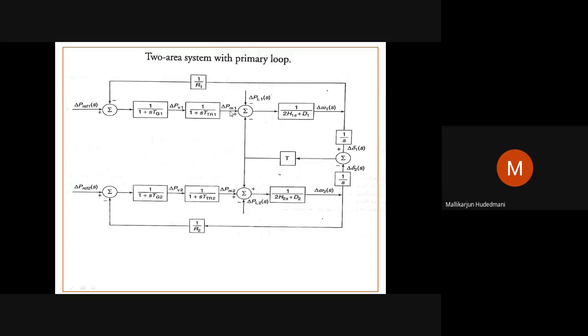more mechanical power. It means to say, if there is a drop in frequency in an area, this is fed back via the droop characteristics of the governor mechanism to the reference set point, and these two together produce an error. That error is nothing but a stimulus to the governor. The governor will reflect that change required into a displacement of the valves. Valve opening is a mechanical displacement, nothing but higher fuel or lower fuel, depending upon the value, caused on the turbine. According to the displacement, the turbine will change its mechanical output.